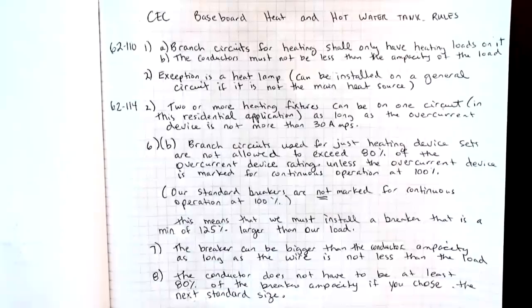Branch circuits used for heating devices are not allowed to exceed 80% of the overcurrent device rating, unless the overcurrent device itself is marked for continuous operation at 100%. Our standard breakers in Canada are not marked for continuous operation at 100%. This means that we must install a breaker that is a minimum of 125% larger than our load.